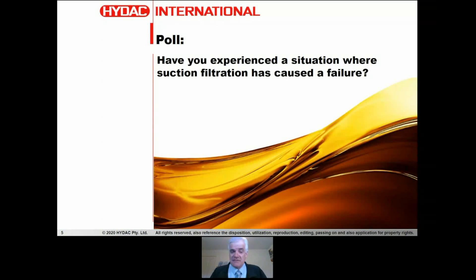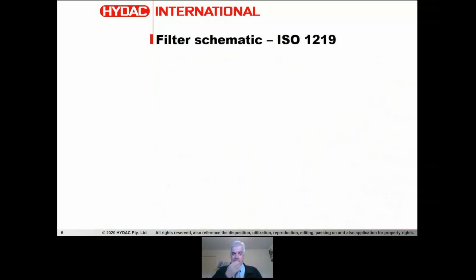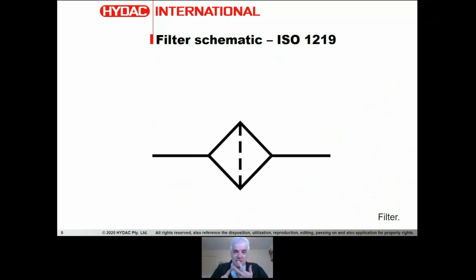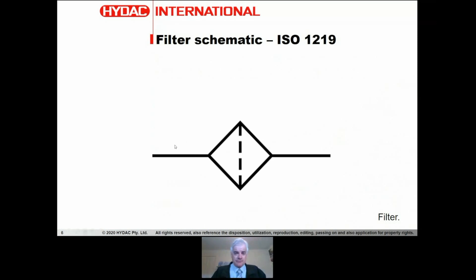One thing I haven't done is discussed the schematic symbol for a filter. According to ISO 1219, the symbol is in a diamond shape. A diamond shape represents a preparation device, so things like heat exchangers, drying devices, and filtration - these prepare the fluid. Preparation devices are shown in diamonds. The strainer is represented with a dashed line indicating straining as fluid passes through.